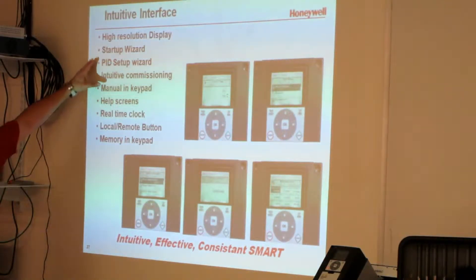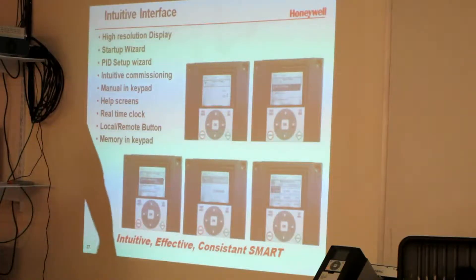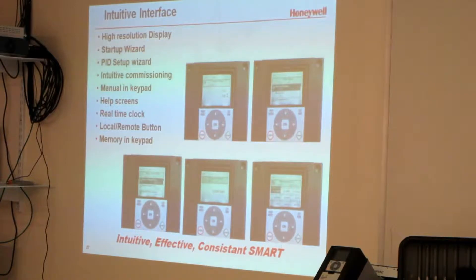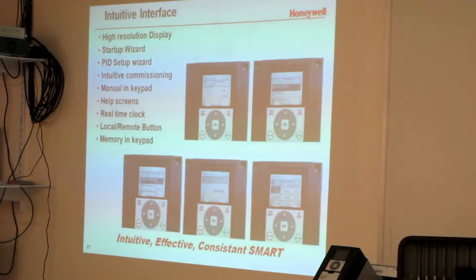There's a startup wizard, so when you first start up it says use the startup wizard. Then it'll ask you what's the horsepower, what's the voltage, what's the speed going, acceleration time and deceleration times. It goes through all that stuff in a question and answer format and it's set up.